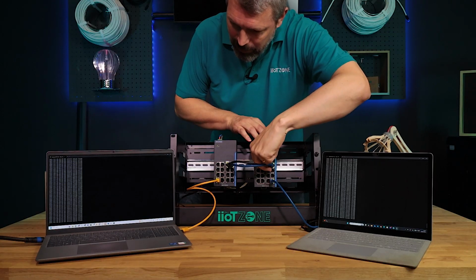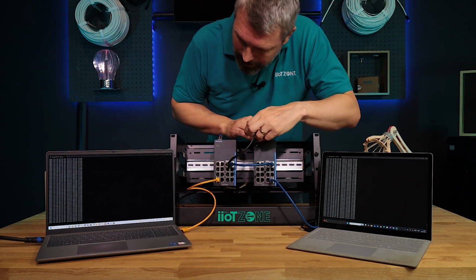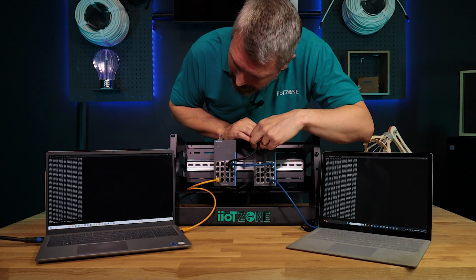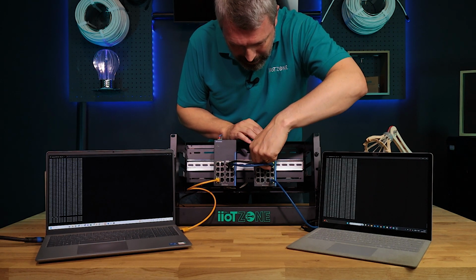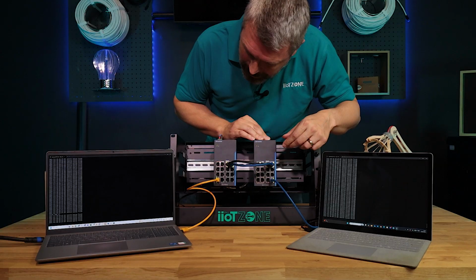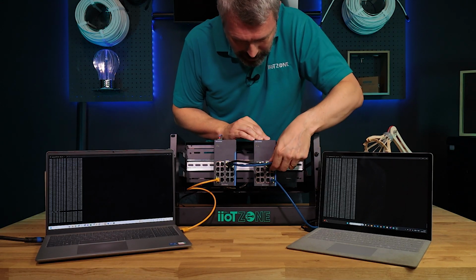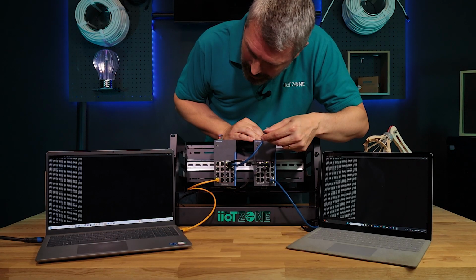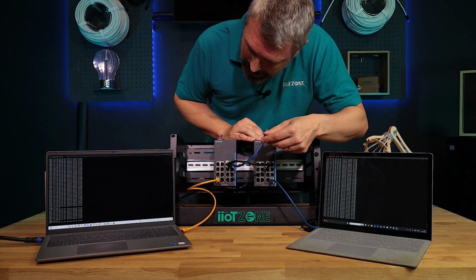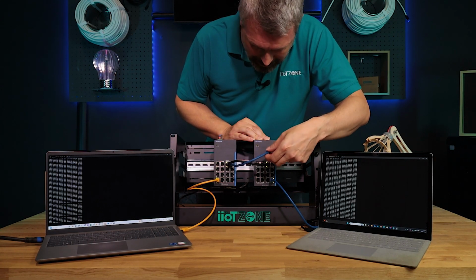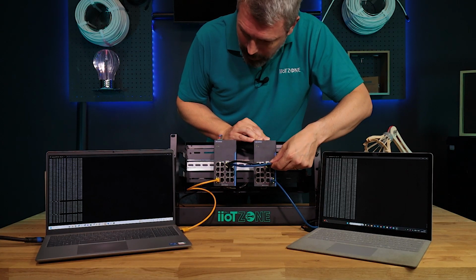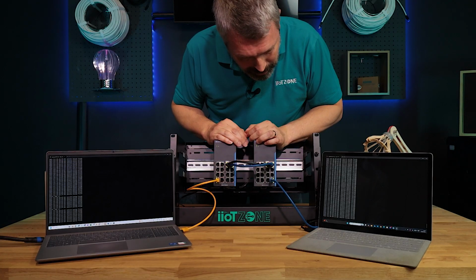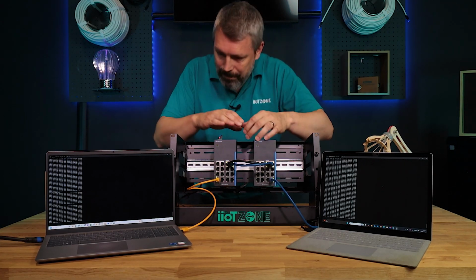So we pull one cable, and we should see at most one dropped packet, and then we're back to pinging again. Restore that connection, and then we're going to pull the other part of the ring connection out. Again, at most one dropped packet, then we're back to normal again. And then when we reconnect our ring, both devices are pinging each other without any problems.